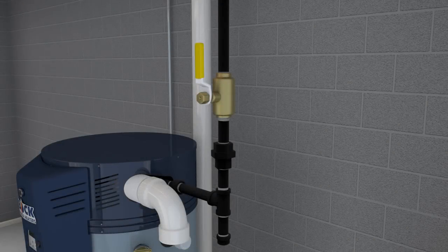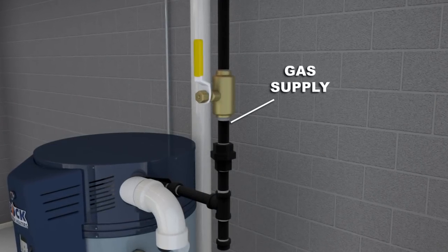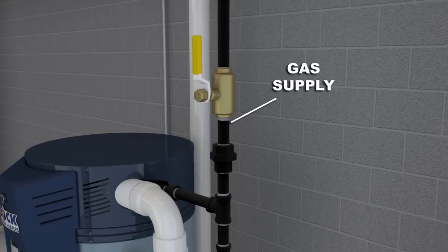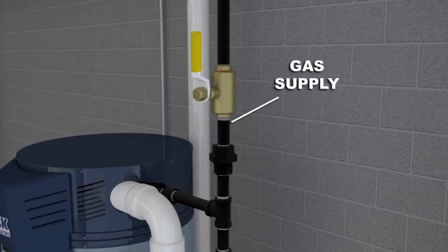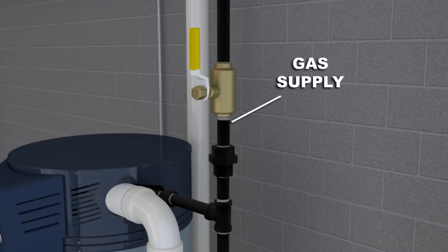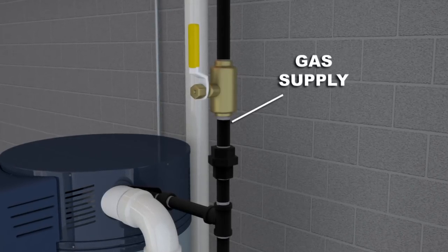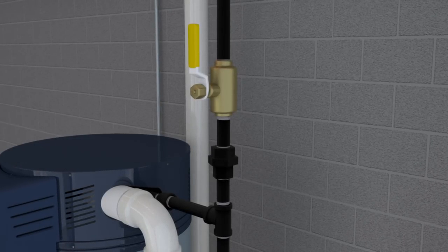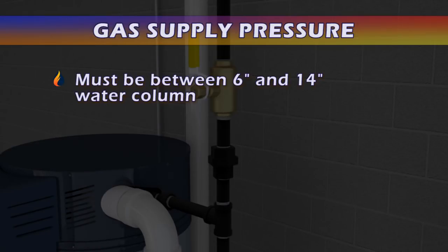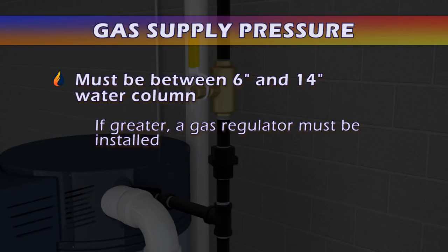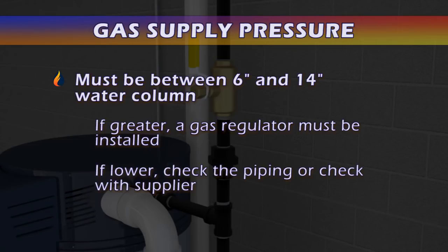The gas supply is attached using appropriate connections conforming to local codes and practices. This usually consists of a main gas shutoff valve, union, T, and sediment trap. The gas supply pressure must be between 6 inches and 14 inches water column. If the gas pressure is greater, a gas regulator must be installed. Check the gas supply piping or check with the supplier if the pressure is too low.